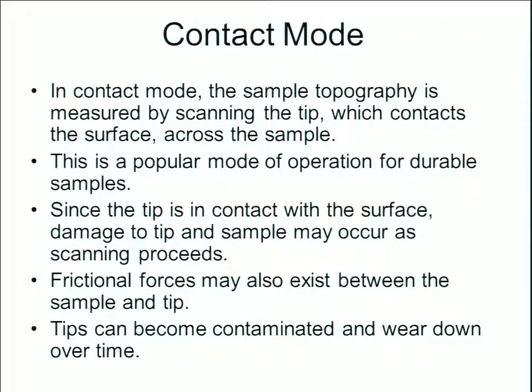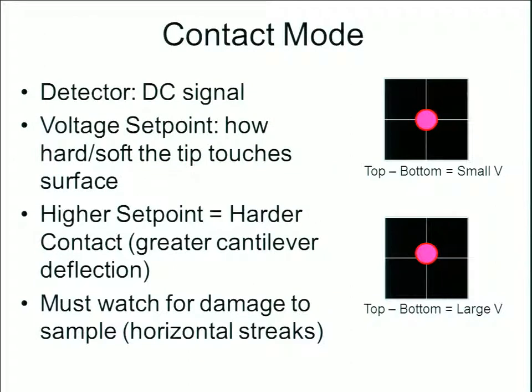Tips can quickly become contaminated and wear down over time due to the fact that they are in constant contact with the sample below. In contact mode, the detector provides a DC signal. We would start with a voltage set point, which allows us as an operator to determine how hard or soft the tip will touch and press down onto the surface below.